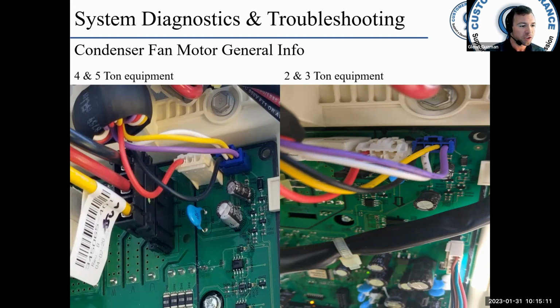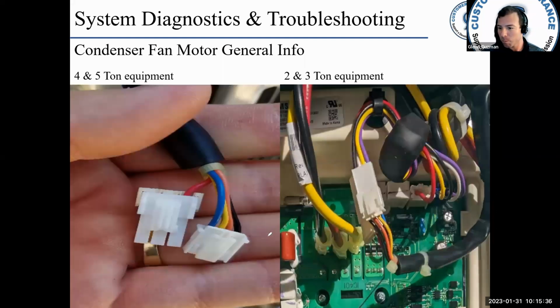But the fan motor on these units has 5 wires, and it's 240 to 373 volts DC. You have red on a single plug, and then black, white, yellow, and purple on a separate plug. There is also an intermediate harness between the VFD and the fan. I'll show you a picture here. If you look on the right, you can see the 2 plugs. The wires come through a choke, and then they go into this plug here. This is the actual fan motor here, and it goes to the fan motor that way. So we have an intermediate harness from the VFD to this point right here.